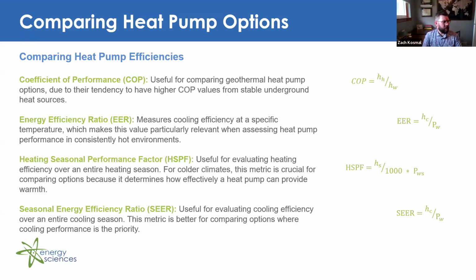And then lastly, we have our SEER, seasonal energy efficiency ratio. And just a reminder, that is your cooling output during the season divided by the electrical power consumed during that season. So SEER is useful for evaluating cooling efficiency over an entire cooling season. And this metric is better for comparing options where cooling performance is the priority. Again, in those southern states like Florida or Texas.